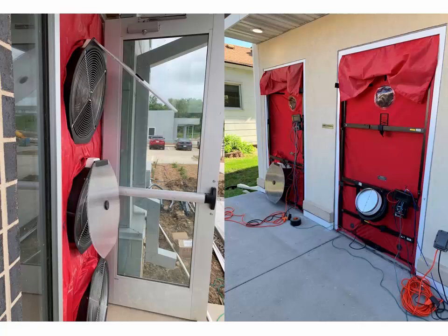Because we needed to depressurize the entire building for our individual unit leakage tests, we were essentially getting a repeat test for the whole building leakage, even when we were using these dampers. And as it turns out, our flow measurements were not that far off from an unimpeded initial measurement. So although these aren't fully calibrated, they actually don't impede the airflow too much.